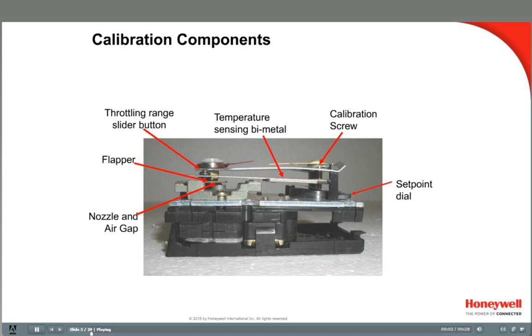Here you can see the nozzle flapper assembly. The nozzle allows air to bleed off, reducing pressure downstream. The flapper sits over the nozzle and blocks or allows air to bleed off. Above the flapper is the bimetal — an element that bends in response to room temperature, which pushes the flapper to a certain distance from the nozzle, controlling the bleed rate.